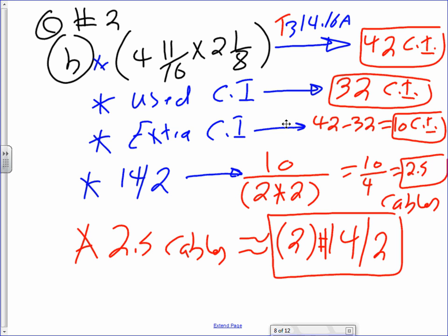How many conductors? 2 times 2 is 4, right? 4 conductors. Any comments, any questions? So I can bring an extra 2 cables. Each cable has 2 conductors and terminate them right in that box, and I still meet the box fill calculation. So that's how we use the boxes, as a junction box.